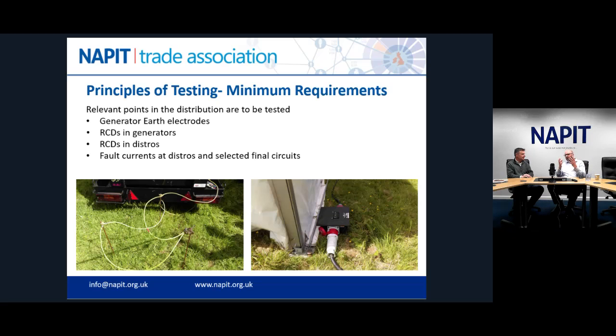And there's a lot to be taken on board, just looking at the picture on the right there. It's a distribution. We have requirements for up to 32 amps for RCD, 30 milliamp RCD, but of course that's only for domestic. We've got the risk assessment for anything other than domestic. I'm glad you brought that up, because the requirement for RCD protection on the 32 amp circuit is intended for a final circuit for people who are going to be holding the equipment and so on. We might have a 32 amp 3-phase distribution circuit, so we wouldn't necessarily apply the 30 milliamps to that because it might not work. That's where it's important to remember the requirement in the wiring regulations for selectivity, and to make sure that we don't get unwanted operation of the RCDs.